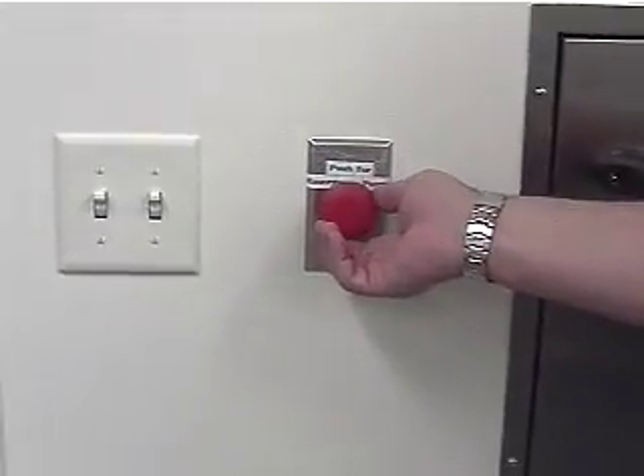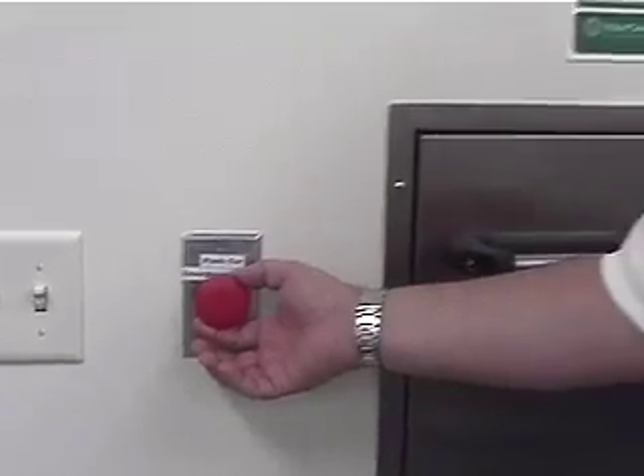Over here, this is one of those emergency push buttons that Matt was talking about, the purge switches that show up on the Phoenix system. So if we push that, it'll show up on the graphic. Push that, you get an automatic go-fast air removal. Full exhaust, no supply, yeah.